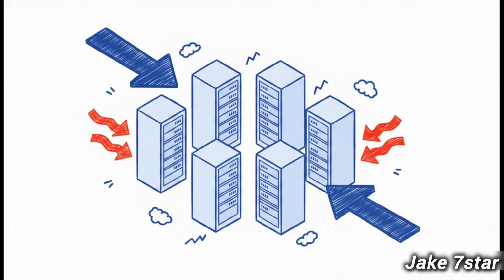If you step inside one of these facilities, you realize the layout isn't just for aesthetics, it's a strict, high-stakes thermal calculation. Server racks are divided into distinct hot and cold aisles. Cold air is pushed with precision toward the front of each rack, and hot exhaust air is captured separately at the back. If you let that cold supply air mix with the hot exhaust air, your cooling efficiency completely collapses. That one simple layout error can add millions to your annual utility bill.